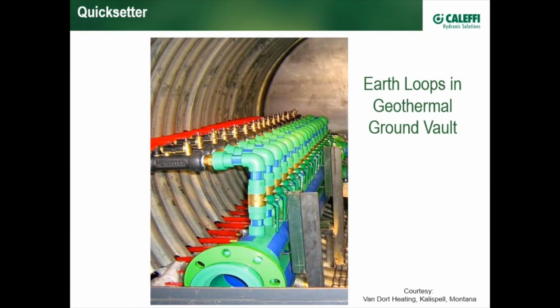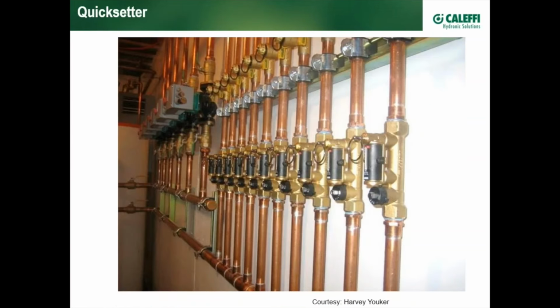More uses of quick setting balancing valves: a geothermal ground vault. The designer has decided to put these type of balancing valves on each of his ground loops, perhaps to make sure that, say, 3 gallons per minute is going through each of his ground coupled loops here. Now, with the confidence that the contractor can set flow accurately using our balancing valves, you can see the reason for their popularity, such as you see on this job here.